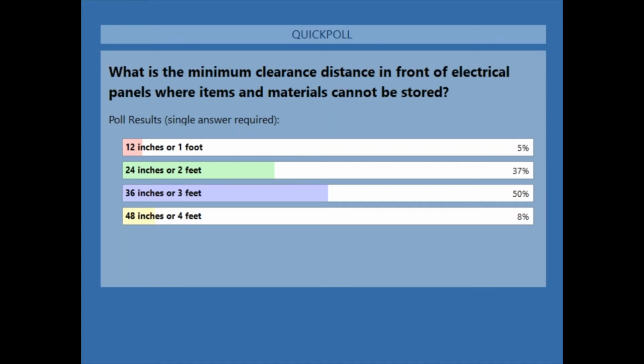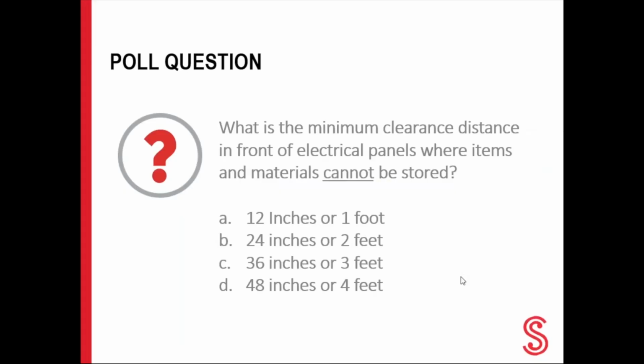Yes, 36 inches or 3 feet is the correct answer. This is to help reduce the possibility of fire from sparks generated from arcing or short circuiting. If you have a power surge, you don't want sparks flying out of your box. The 36-inch clearance is all the way around as well, from top to bottom and straight across.